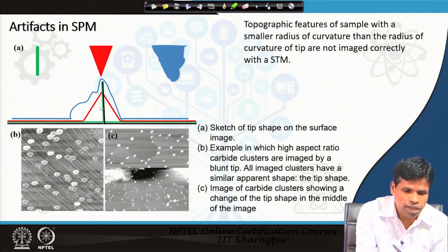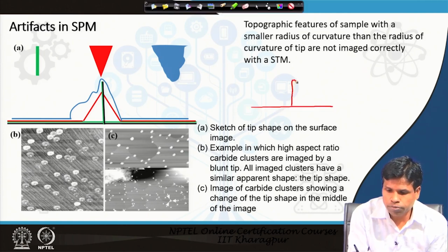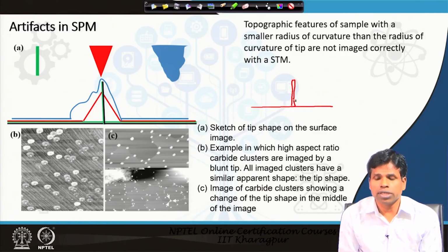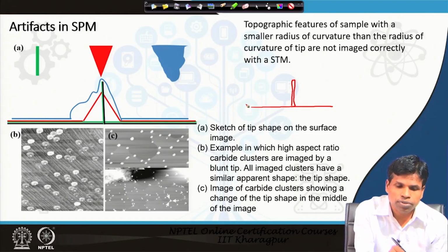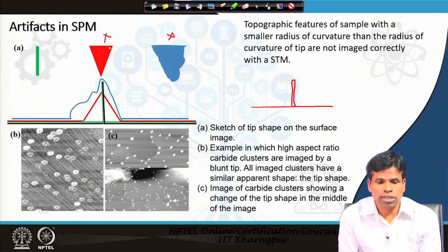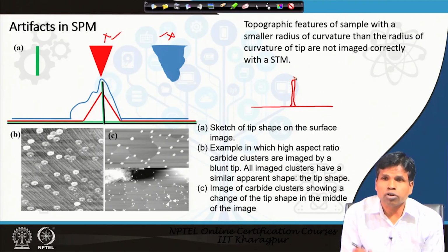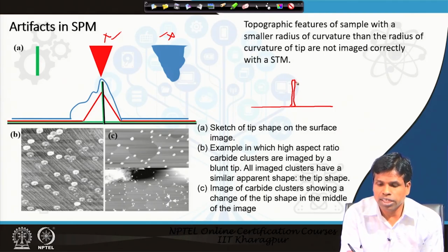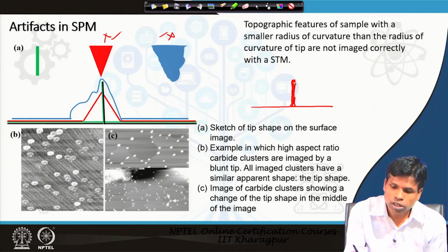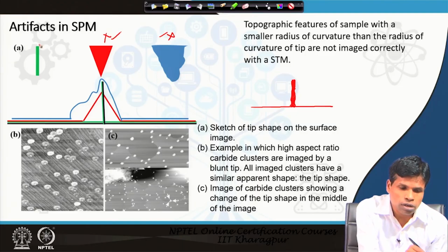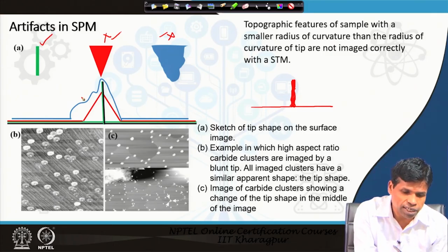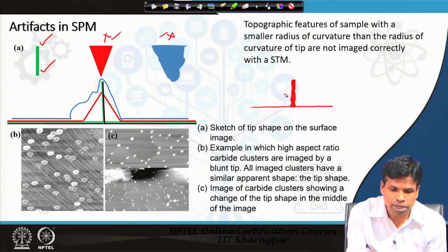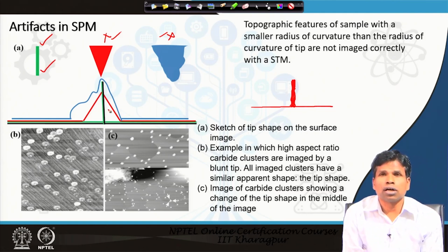As you see here, let us say we have a one-dimensional feature on the sample, and this type of one-dimensional feature cannot be studied by this type of tip. So, in order to get the correct image of a one-dimensional feature, our tip should be of similar aspect ratio or better aspect ratio. Aspect ratio is the ratio of the height to the width or thickness. So, if we choose a tip suited to one-dimensional features, then only it can give, like here by using the green tip, an image of the one-dimensional feature using the STM.